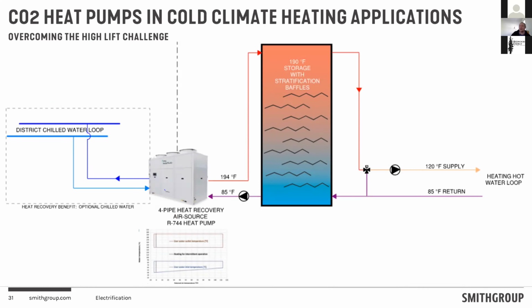So not a domestic hot water system trying to be a space heating system. The key is blending down that 190-degree water with my return water loops. I'm just injecting the hot water to get it back up to 120. But that lets my tank continue to stratify. It allows me to store water at a very high temperature in a very compact footprint. It gives me tons of flexibility in load shifting, drawing out my heat pump production time, so I don't need as big of a heat pump.